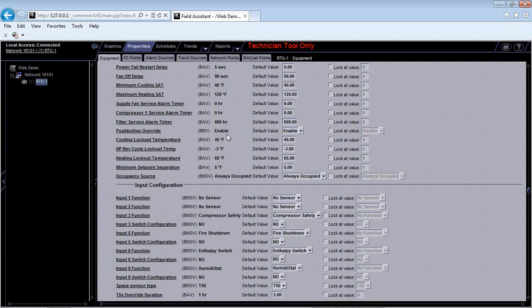So let's say that you wanted to maintain the supply, or you wanted to do a service call every time the supply fan runs for 600 hours. If I type in 600 here and I hit OK, my timer is going to start running, okay? Once that timer expires, I'm going to put an alarm up on my graphic that's going to say supply fan service alarm, okay?